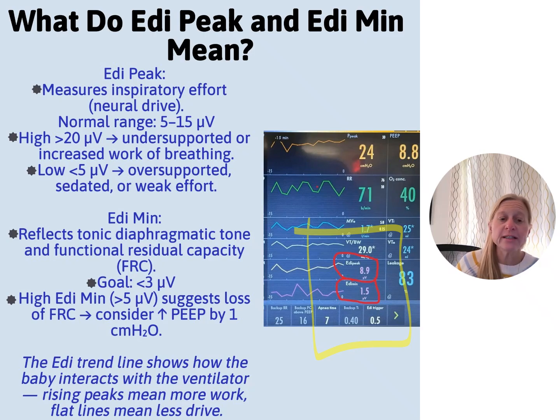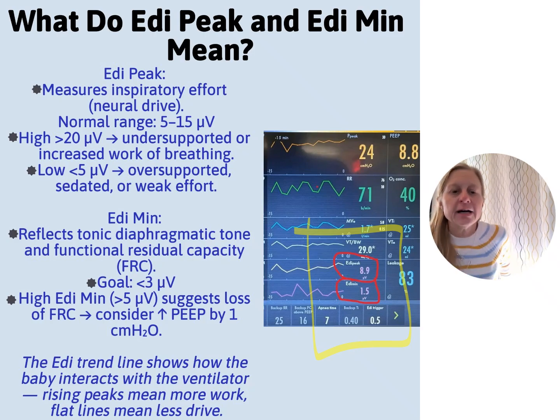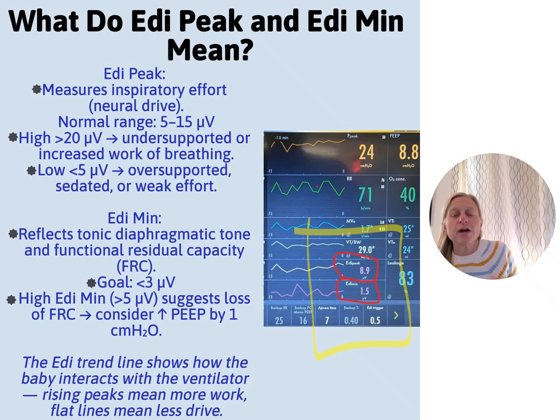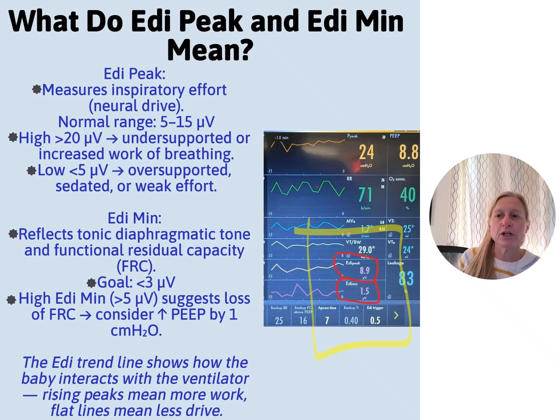So the Edi trend line shows how the baby interacts with the ventilator. Rising peaks mean more work. So as you can see here on that peak, we had one peak and then it's kind of flat, which is pretty good. It means that there's not as much pressure and drive coming from that ventilator. So that's kind of what you're looking for. I want you to remember these numbers because we're going to need to know them as we move into our NAVA level, which we're going to discuss next.